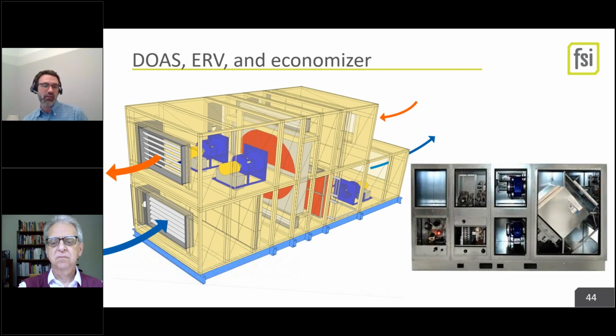So if you're cooling to 75 and most of your building has gotten to cooling where you'd want to use free cooling, your exhaust airstream is 75, and your incoming airstream needs to be something less than 75 to get the cooling. So it depends on where you are in your cooling and how much each individual zone is ramped up into cooling to actually need it. But you probably are not going to cool that air down, particularly given that we've given a DOAS tempering limits. They can only cool so far and heat so far. So that's really your threshold for a sensible version.